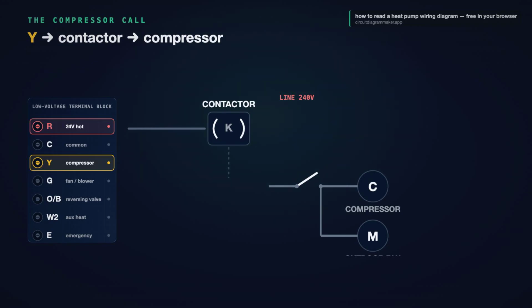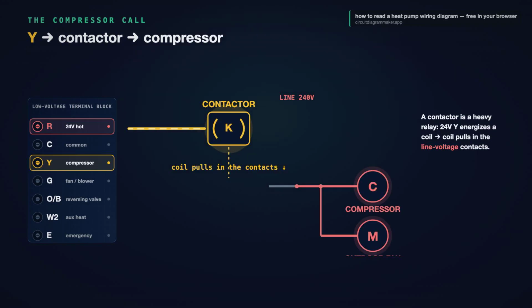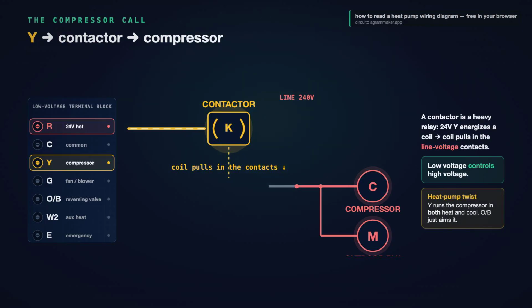Next is Y, the compressor. Trace Y, and it runs to a contactor in the outdoor unit. A contactor is just a heavy-duty relay. The 24-volt Y signal energizes a small coil. That coil pulls in big line voltage contacts, and the compressor and outdoor fan get their power. This is the low voltage controls high voltage idea, same as any air conditioner. But notice something a furnace diagram never shows. On a heat pump, Y runs the compressor in both heating and cooling.